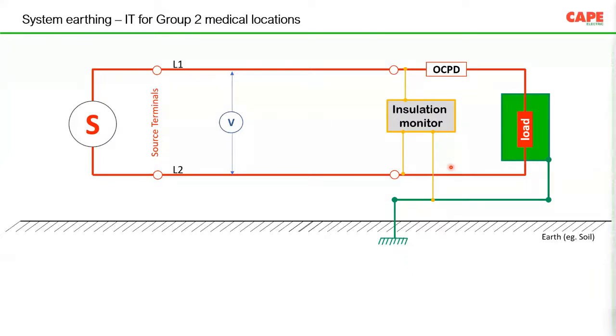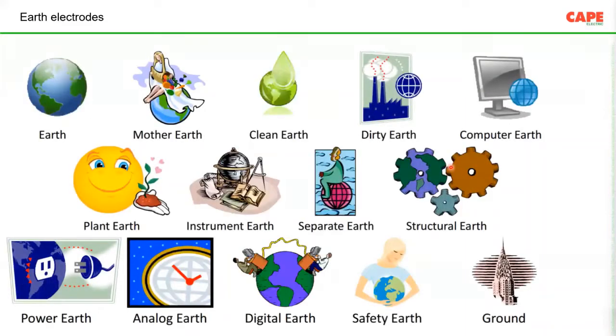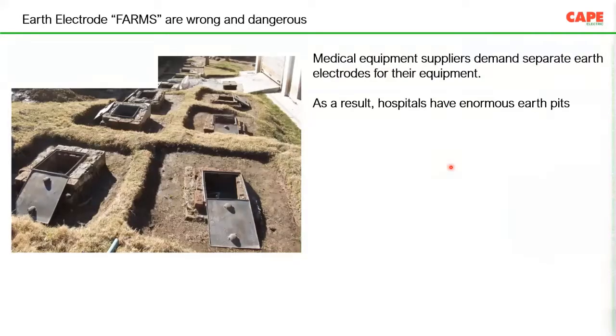What I wanted to tell you is, don't think that by making a hospital IT panel you achieve the entire safety. No, it is not like that. You have to have so many safety measures. One of the safety measures is the medical IT system. But whenever it comes to the earthing system, actually the first part we are missing is earthing. And everywhere, so many earth electrodes. There are hospitals with more than 150 to 200 earth electrodes all around. So we make a kind of an earth farm.